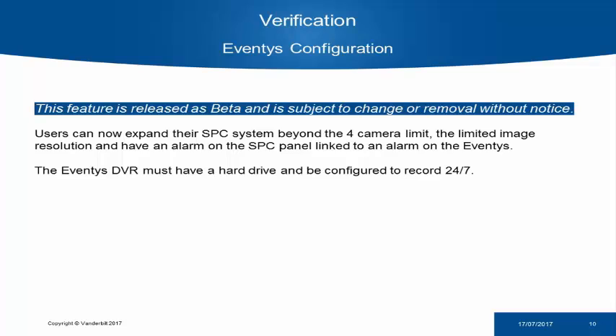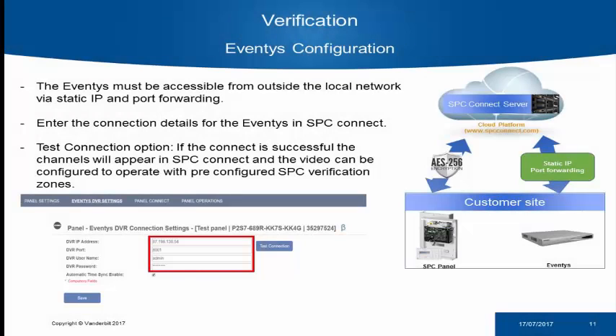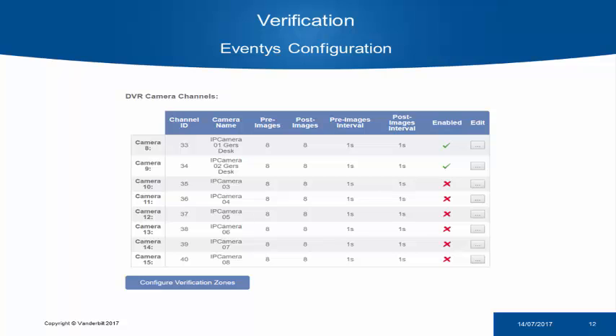Entering the IP address, port, and username, we can verify that the connection exists. Once this is achieved, the channels that are configured on the Eventys will appear. This is similar to the settings on the SPC panel in terms of pre, post, and interval between images. We can configure this on SPC Connect. Please note that the Eventys must be configured to be recording in order for verification to be obtained from the NVR.